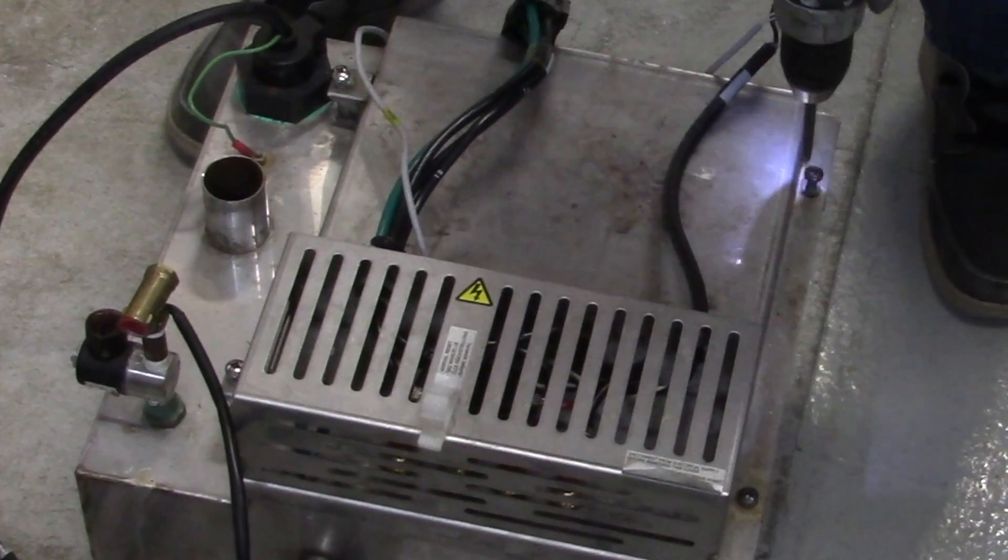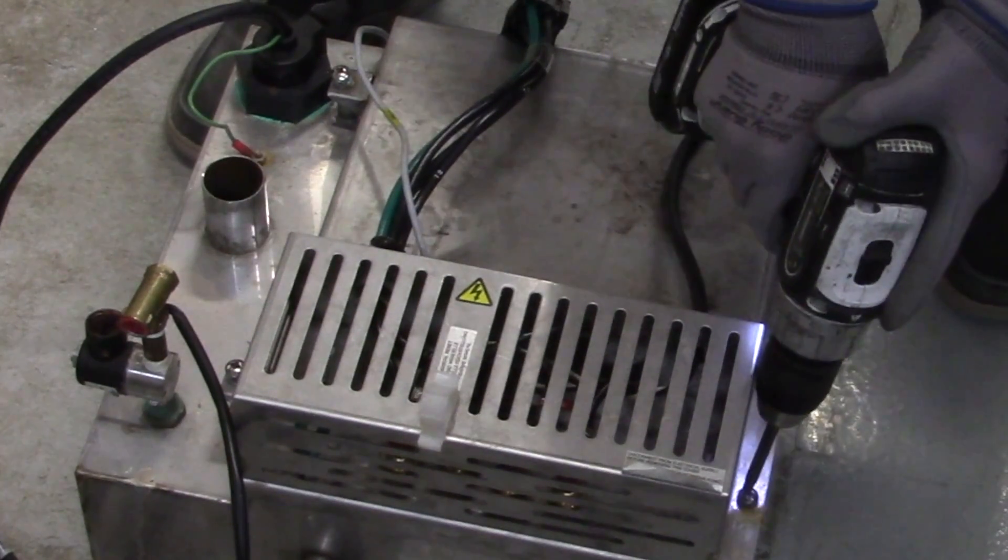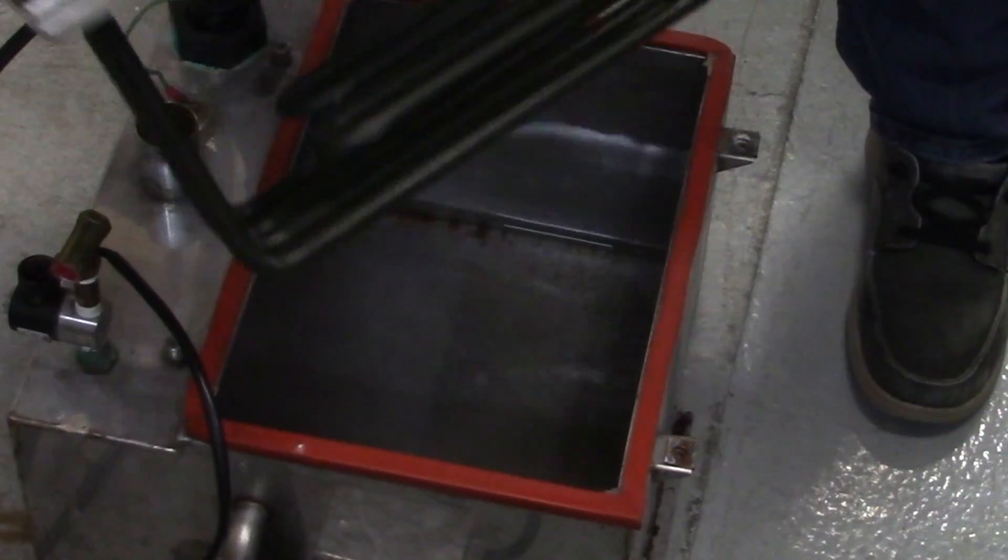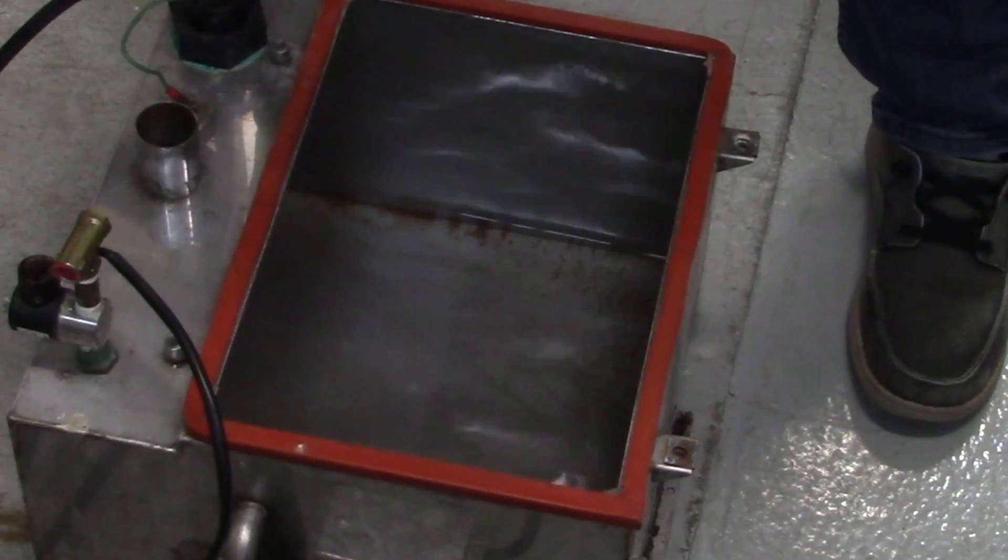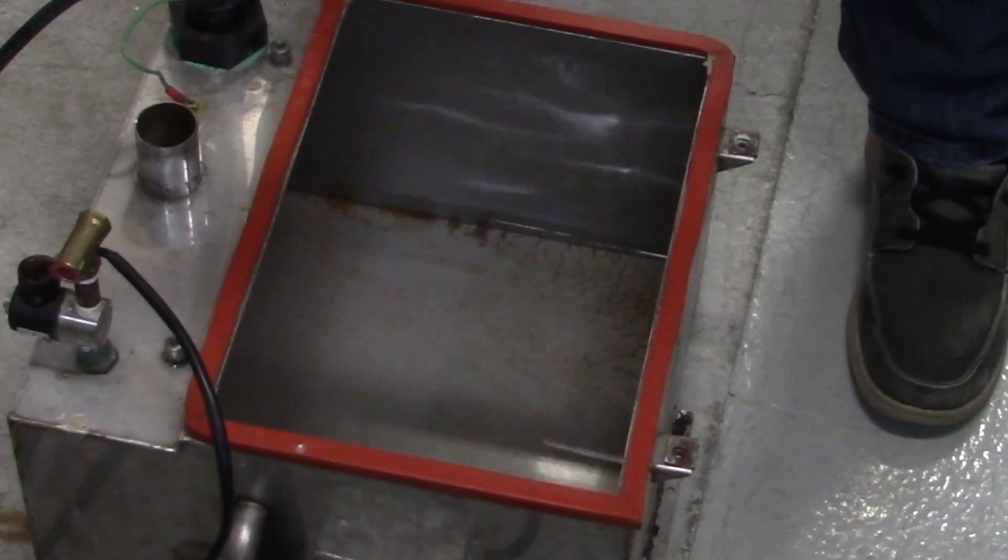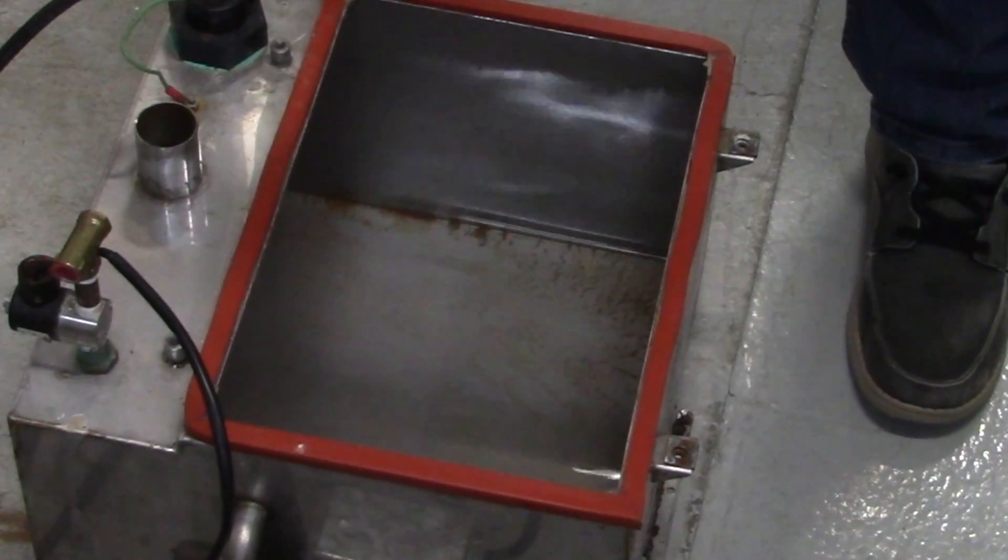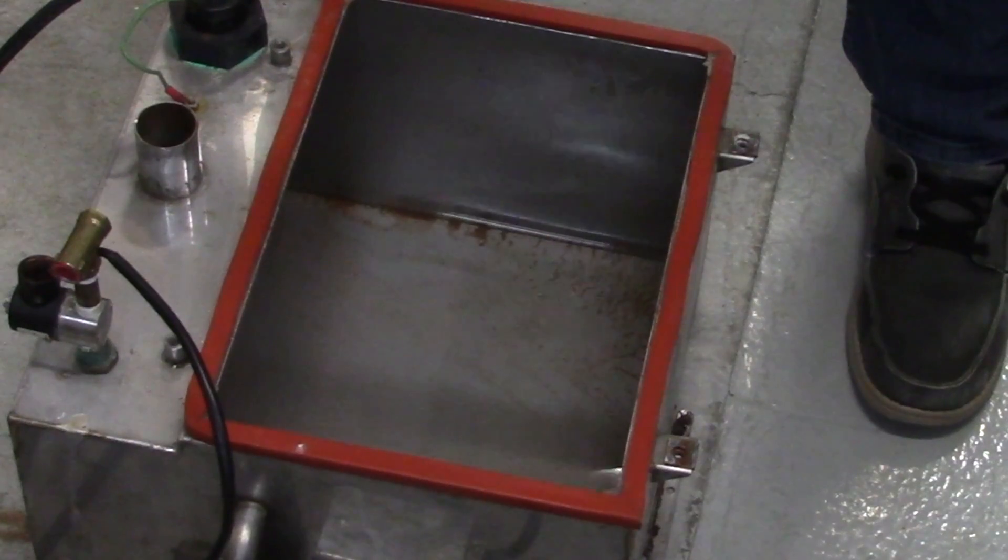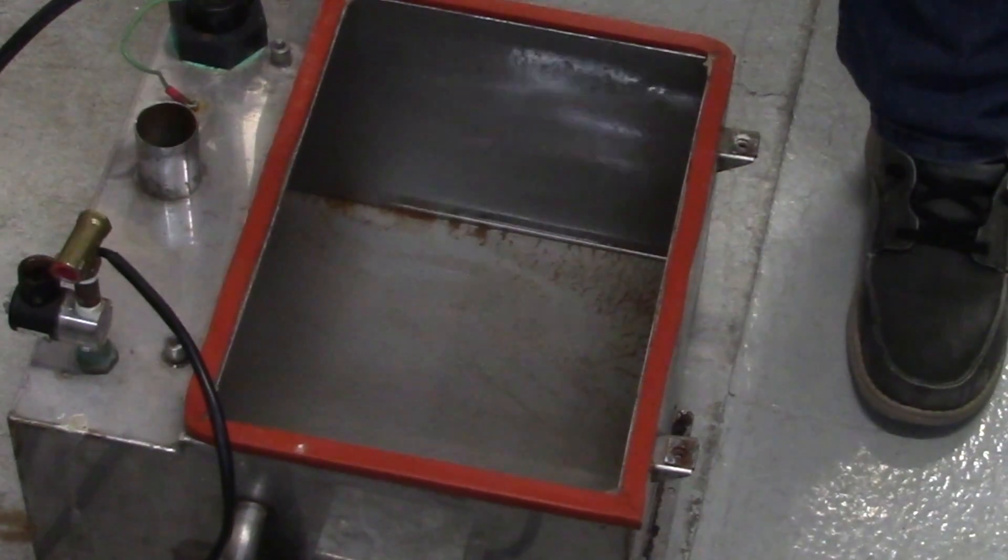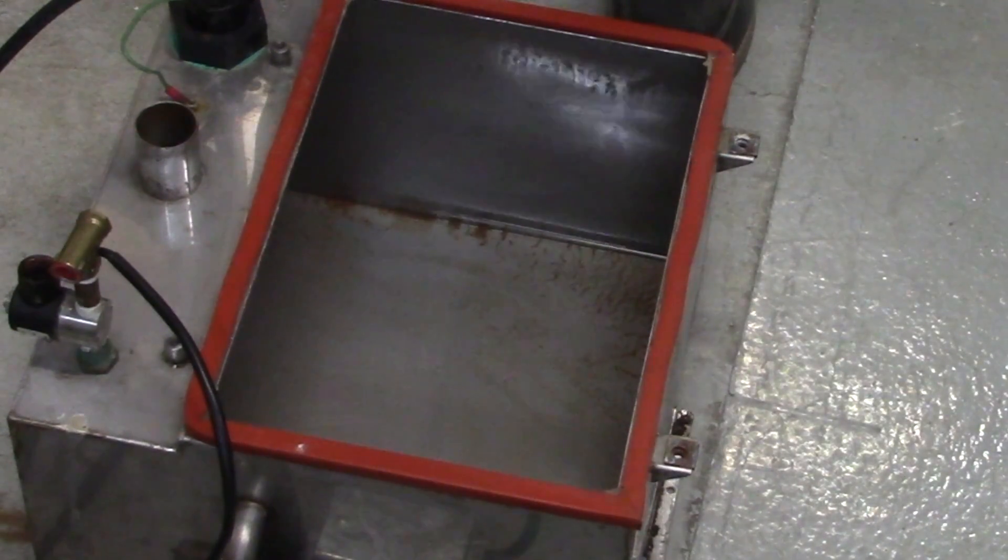The best way to determine how often your humidifier needs maintenance is to remove the tank cover and inspect it for mineral deposits after three months of duty. Hours of operation and duty cycle will determine your maintenance schedule, as will water quality. Clean the tank interior using a putty knife or similar flat instrument.